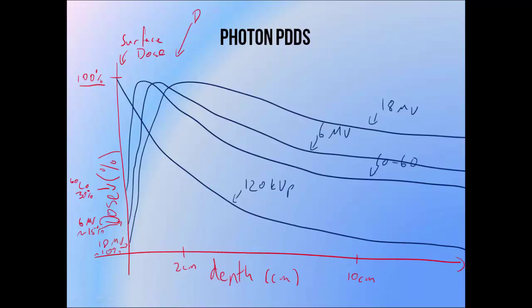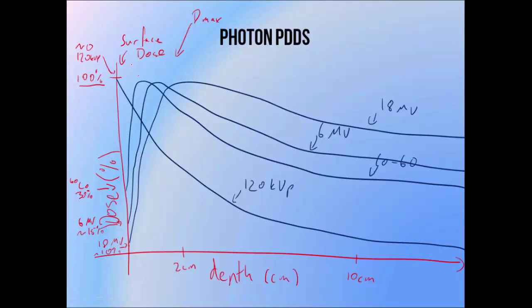The depth of maximum dose, or D-max, tends to increase with beam energy. We tend to class kV beams as having a D-max of 0, depositing maximum dose at the skin surface — though there is a small buildup region in low energy beams too, it's just very small and we don't generally see it on measurements. A cobalt-60 beam has a D-max of around 0.5 cm, 6 MV about 1.5 cm, and 18 MV about 3.3 cm, although there is some normal variation in these values.